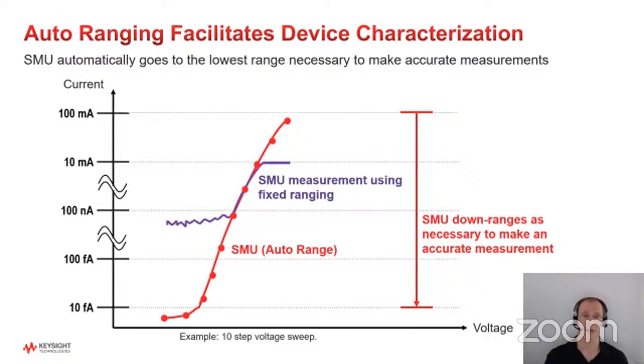It's important to understand that to make low-level measurements, you need to be in auto ranging, so that the instrument can go all the way down to whatever range it needs to be in to make an accurate measurement. But be aware that when you make auto ranged measurements, especially at very low currents, it will take a long time. So if you're making a sweep measurement, expect it to take a long time at the lower part of the curve and then start to speed up as it gets to the higher voltage or current levels.